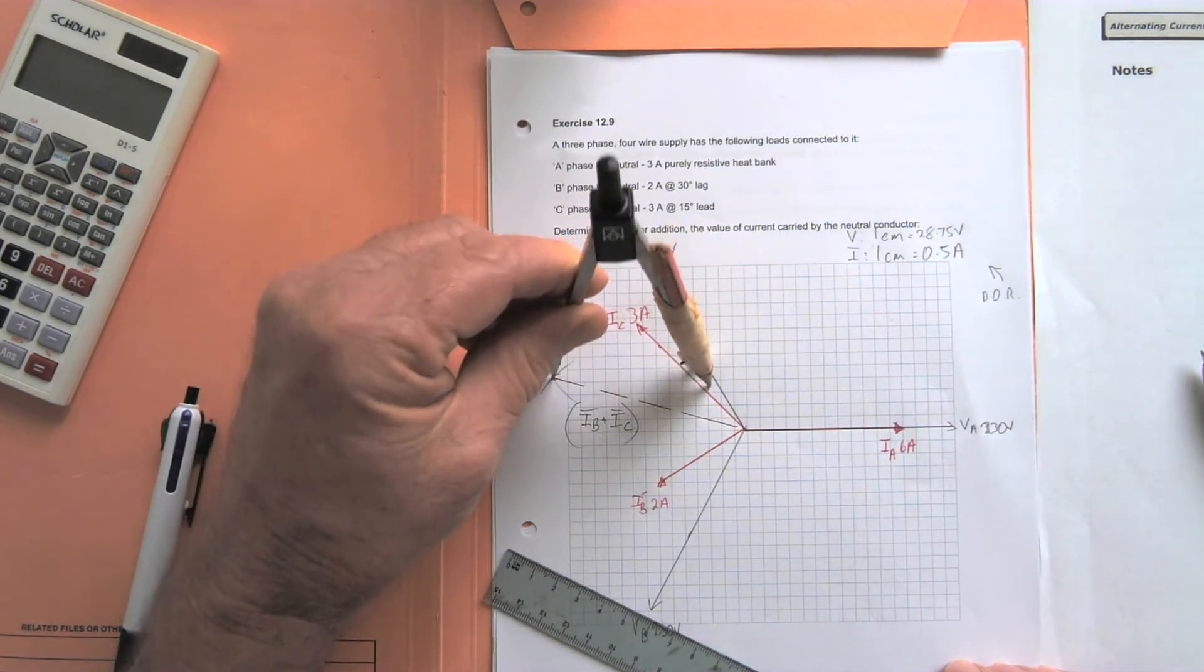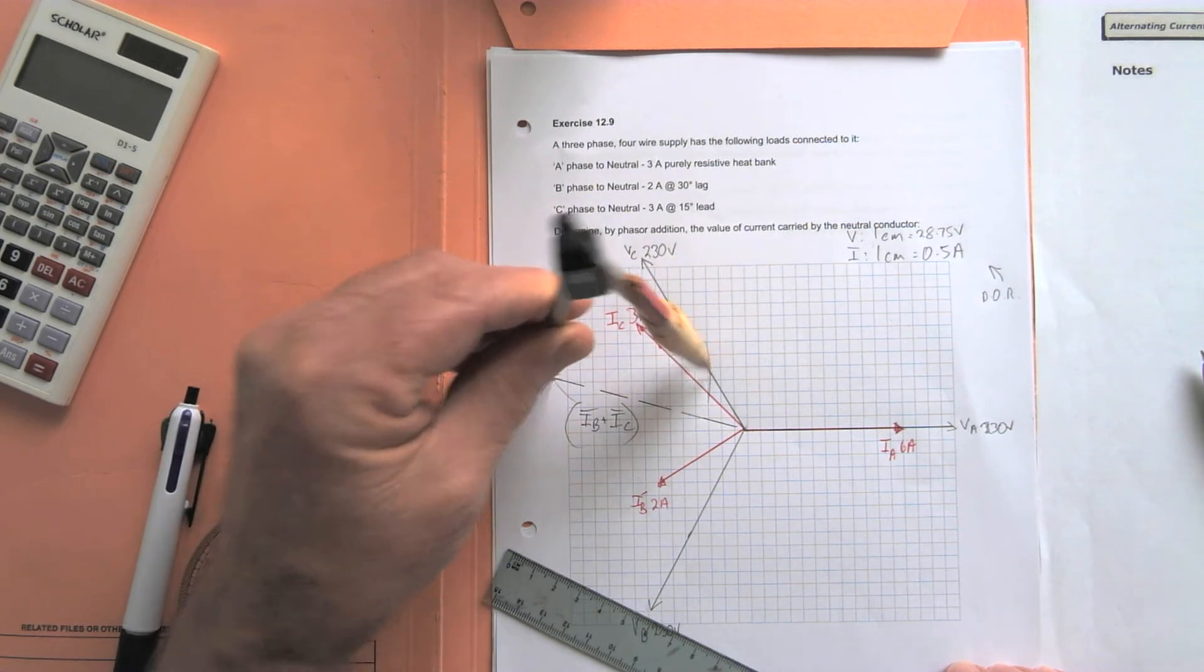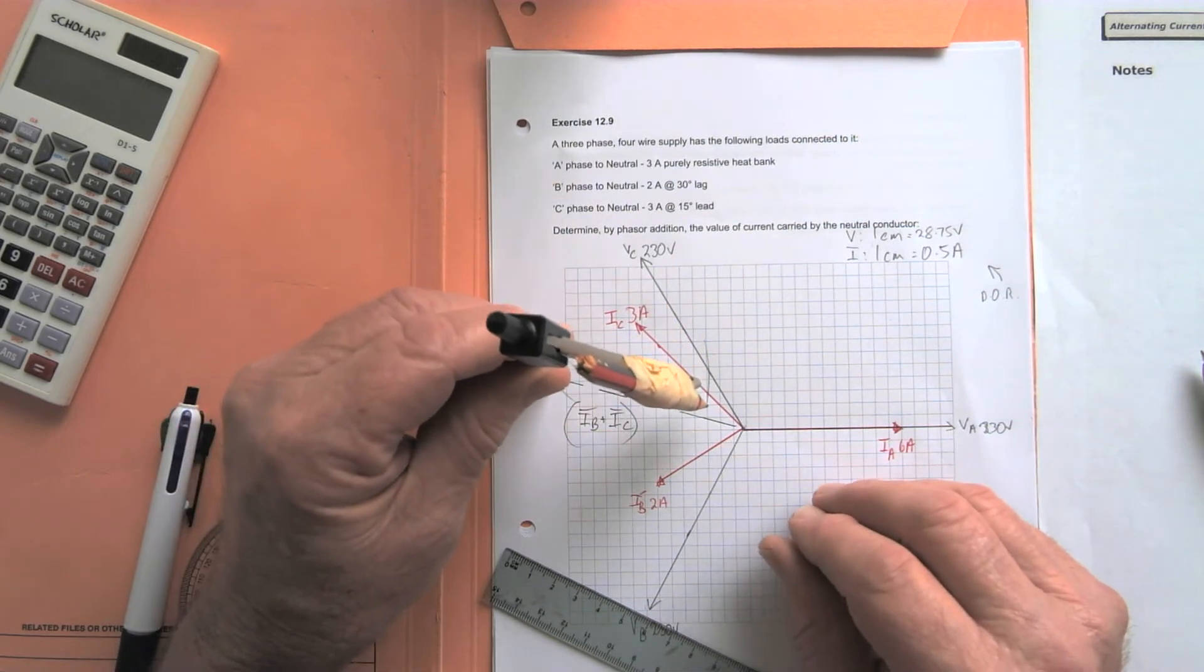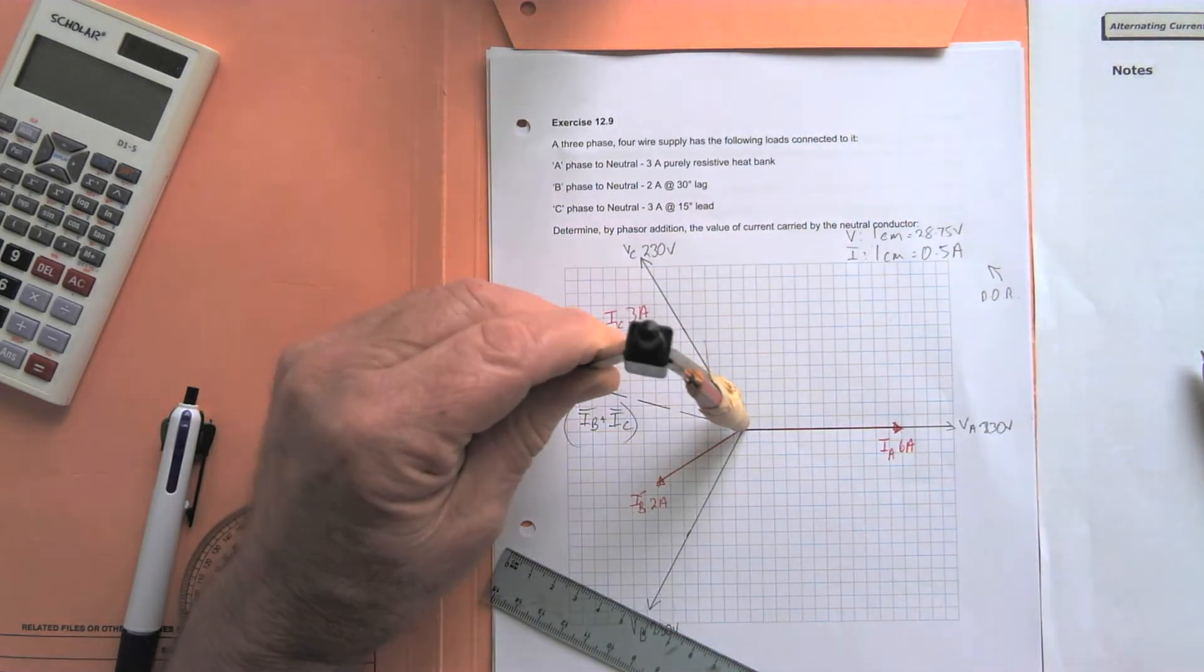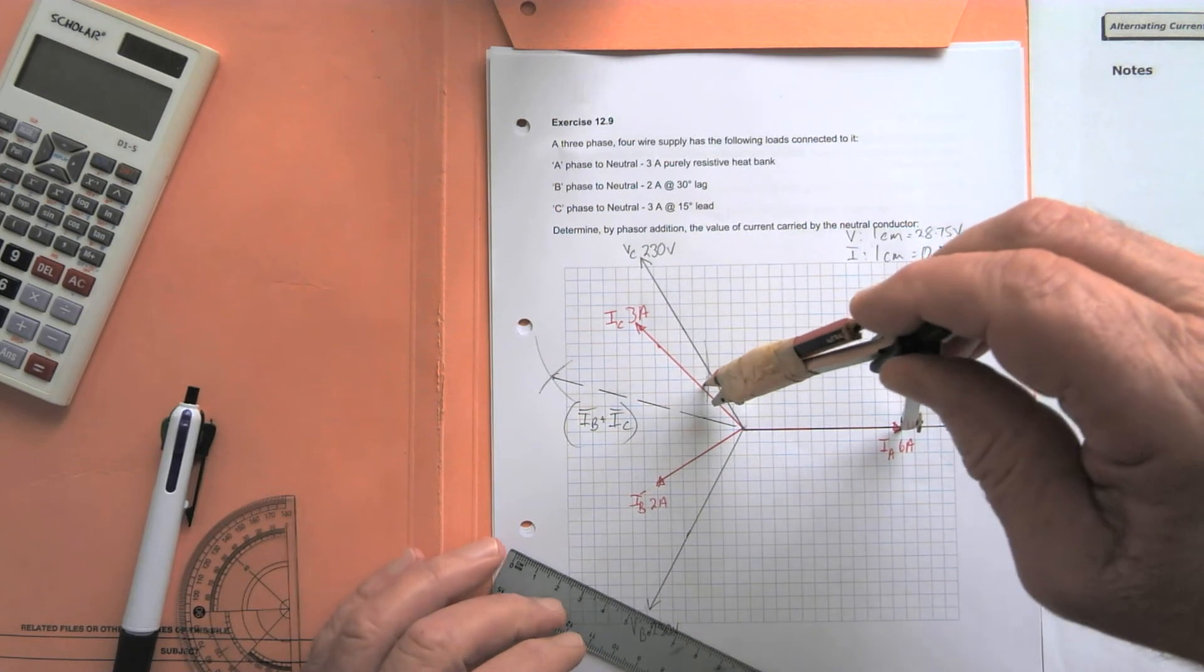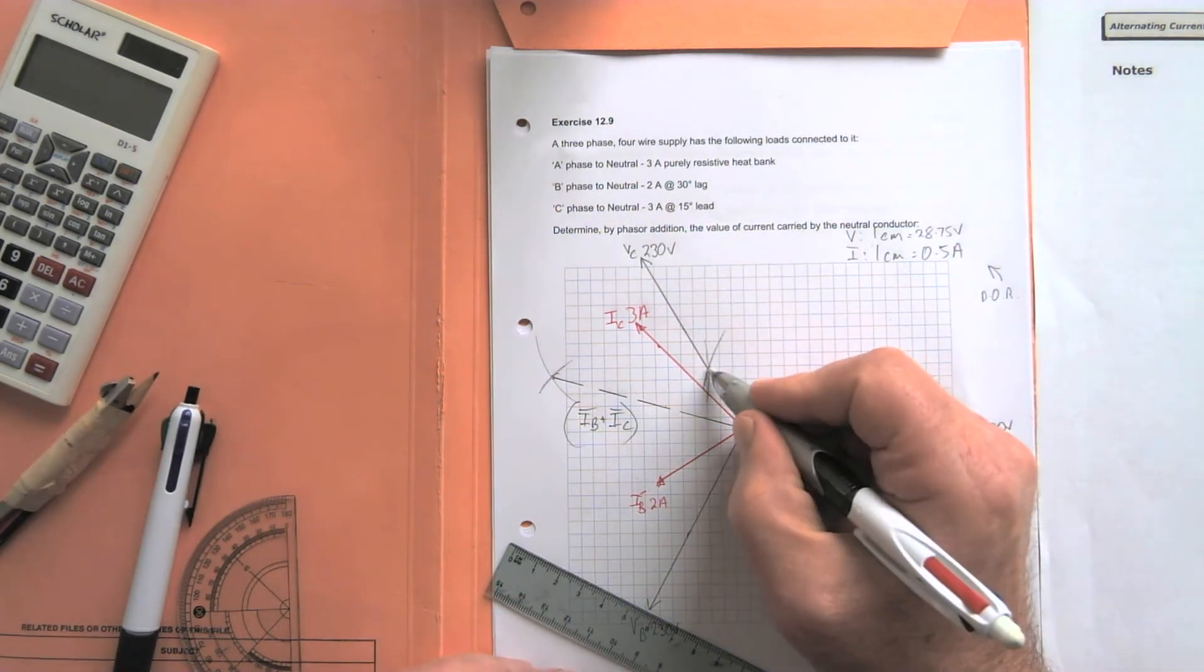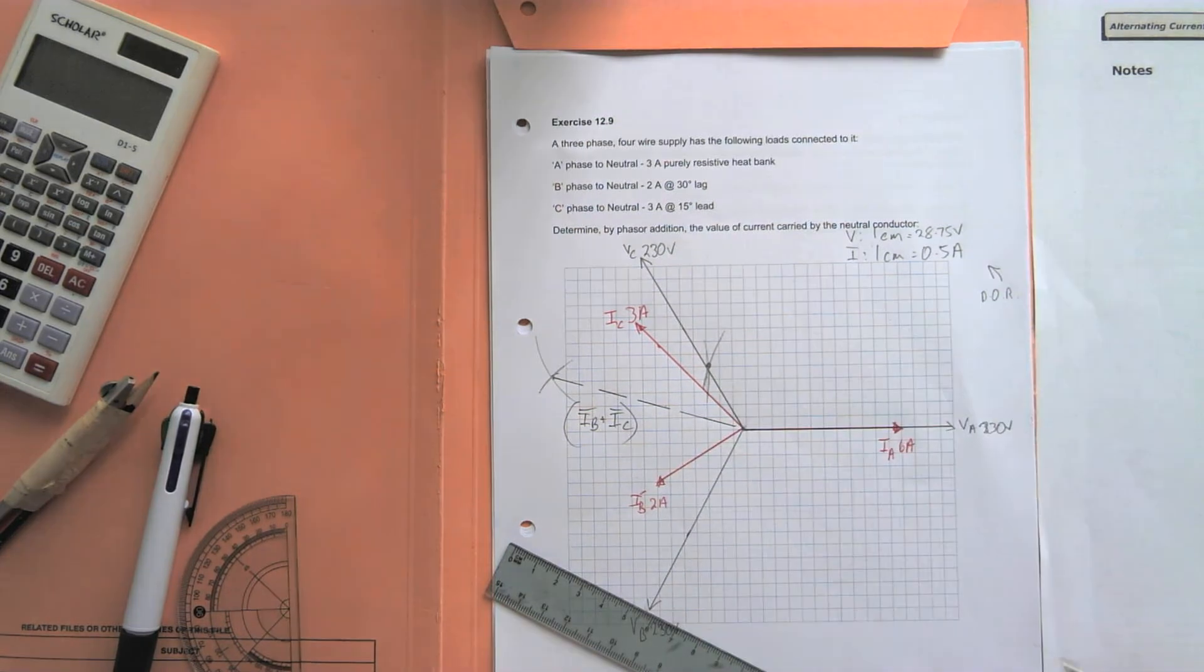And then we take the length of that resultant there and come to the tip of IA to complete the parallelogram. And where those two points meet in there, back to the star point, is your value of neutral current.